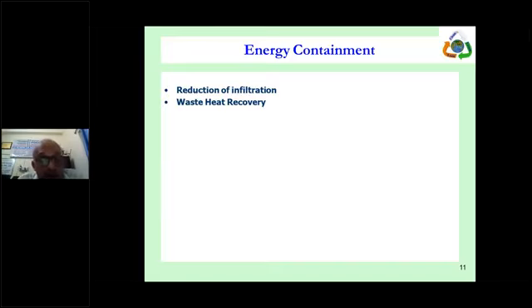You might have seen many air conditioned premises where a lot of infiltration of hot air happens. Hot air from outside comes in through many openings. Some we cannot avoid, but there are many others. I have seen places where, through cable tunnels, cable channels, pipe openings, or other openings left open for maintenance, hot air ingress happens. That adds to the heat and also adds to the dust load. So during the walkthrough, we must notice where this is happening, and the reverse may also happen, where chilled air may be leaking out. So you have to contain: see that unnecessary things don't come in, and something we need doesn't go out.